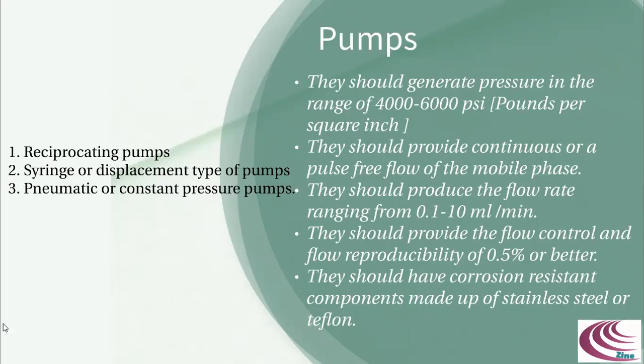The high pressure generated by HPLC pumps doesn't constitute an explosion hazard because liquids are not very compressible. Thus, the rupture of components of the system results only in solvent leakage, and such a leakage may constitute a fire hazard.